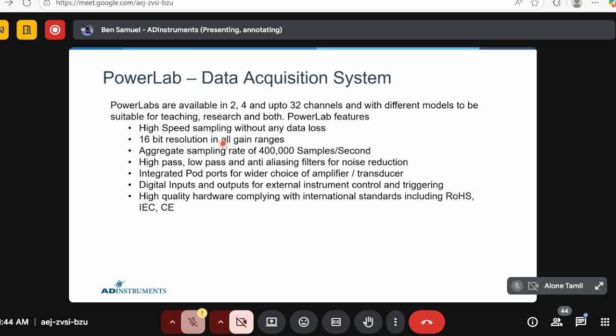So in summary, the reason I'm emphasizing the resolution is that the resolution and the sampling rate of a data acquisition system are very, very important. The signals are very tiny, the medical standards demand high accuracy, and we need a low noise signal. So for all these things to be covered, we use a high resolution DAQ.